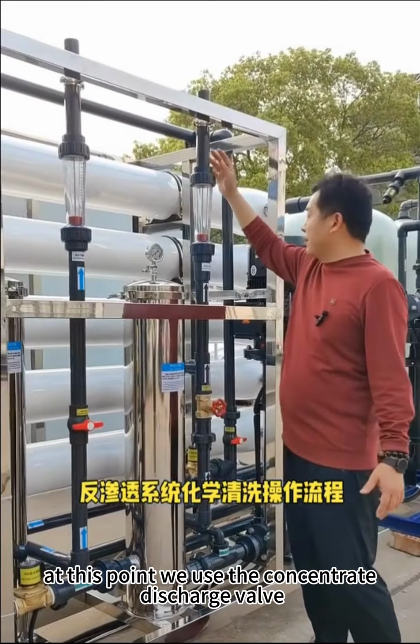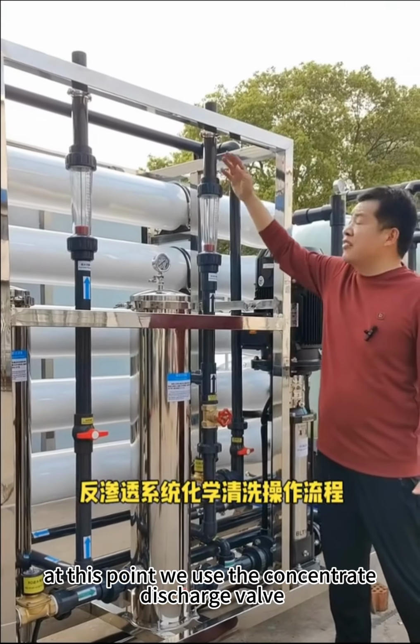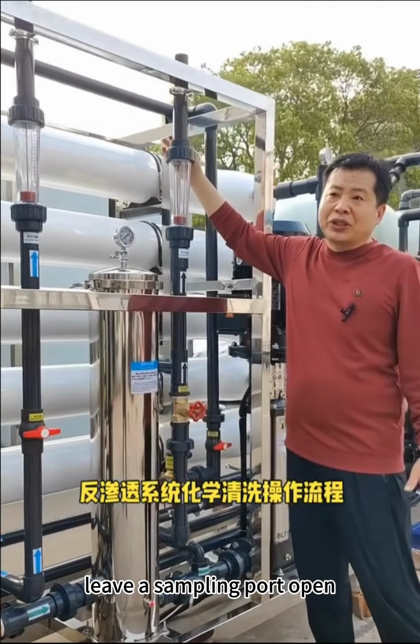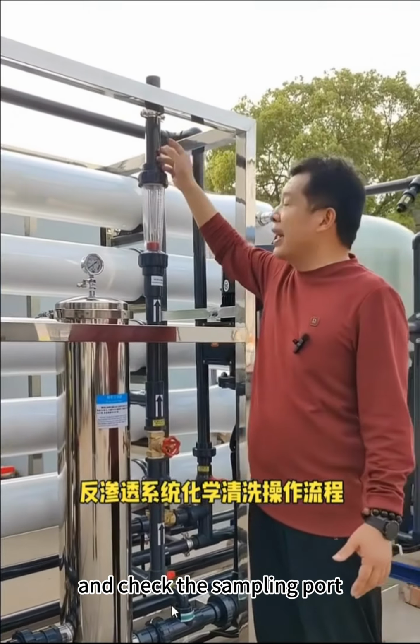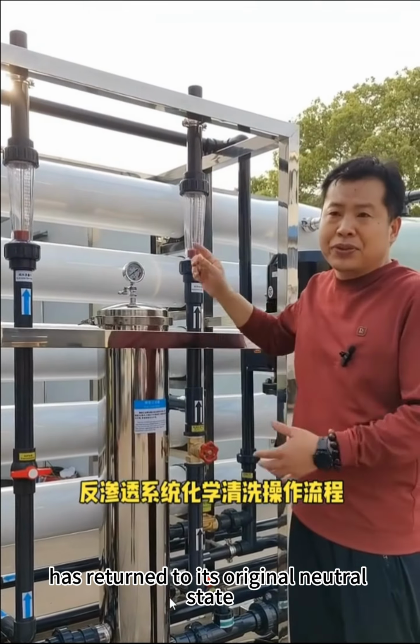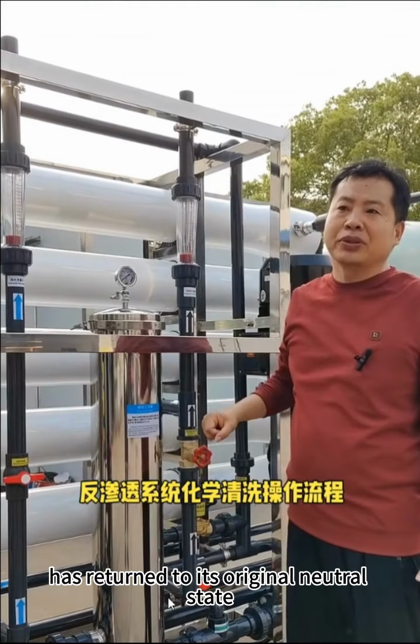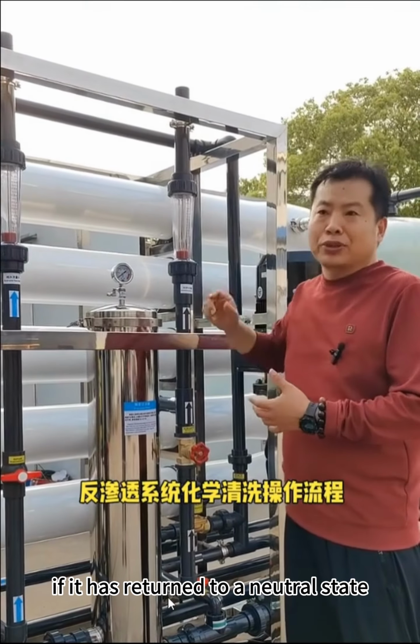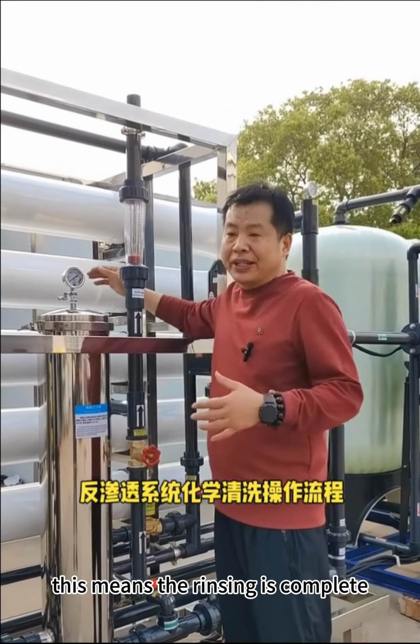At this point, we use the concentrate discharge valve. Leave a sampling port open, rinse for 30 minutes, and check the sampling port to test whether the pH has returned to its original neutral state. If it has returned to a neutral state, this means the rinsing is complete.